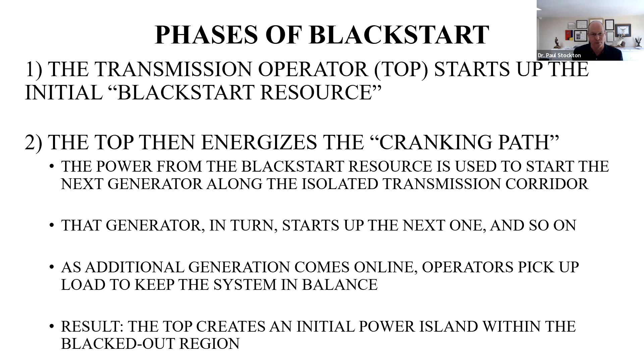As you add generation capacity, you also need to pick up load to keep the system in balance, because grid stability requires constant, close to perfect balance between generation and load. In this process of initial Black Start establishment of a cranking path, you create a little power island within the larger blacked out region.